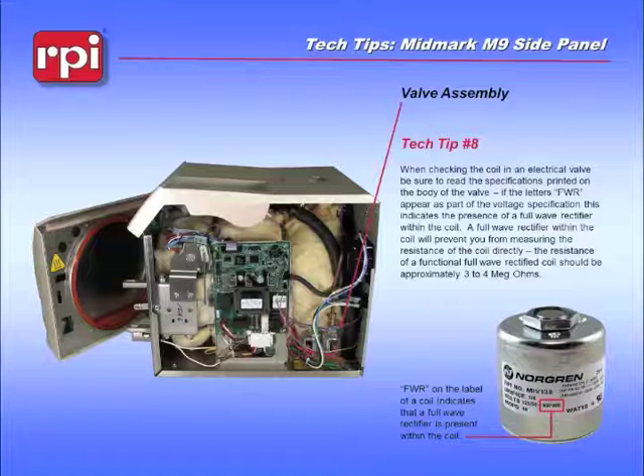But if you're going to refurbish the valves themselves, we need to identify what style valves you've got so we can give you the correct internal materials for that valve. Also, you have the option of just outright replacing the entire valve, including the brassware and the housing and the coil, based on the wear of the valve. If you believe that you're having a problem with the brass body of the valve, the only way to actually fix that is to replace the entire valve. Also, if you are working on the newer style valve assembly, we have it available as a complete valve assembly, including both valves and the brass block, or we have broken it down into individual kits.